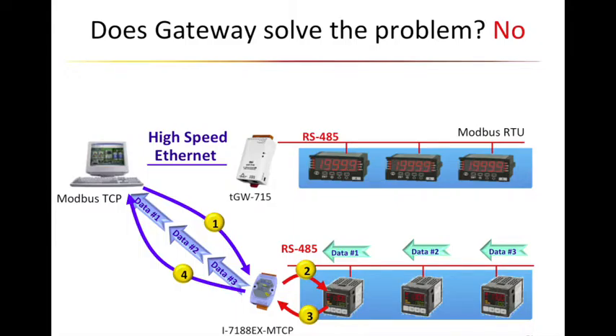The gateway product that uses Modbus TCP to Modbus RTU is quite popular. We have similar products such as i7188EX MTCP and TGW715, etc. For this type of product, it is required to set up the baud rate of the COM port on the gateway and the ID range of the Modbus RTU devices managed by each COM port. When performing communication on the PC, the IP address of the gateway and the Modbus ID are specified. When the commands are sent from Modbus TCP to the gateway, they will be bypassed to the Modbus RTU devices on the corresponding COM port. The setting is quite easy, but it cannot solve your problem.